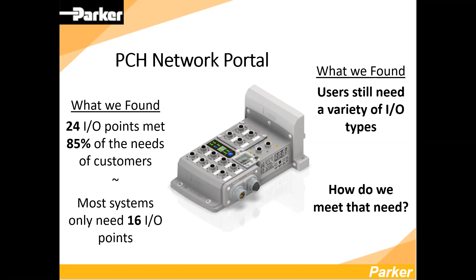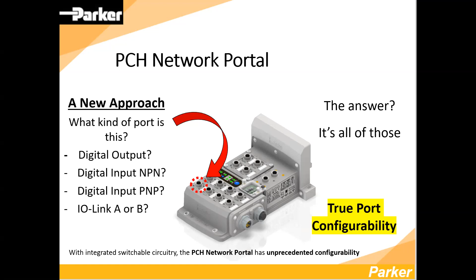What's also unique to Parker in this sense is that, based on a configuration, you can configure an input as a PNP input or an NPN input. With anybody else, that's actually a different part number, a different piece of hardware, and it's either all NPN or all PNP. But with this module, the PCH portal, you can take pin 2 and make it an NPN input, and take pin 4 and make it a PNP input, right on the same port. That's part of our true port configurability. And you can also enable it as IOLink since it is an IOLink Master, but you have the choice of doing that.